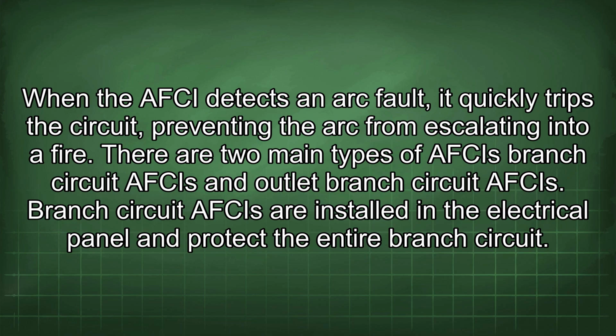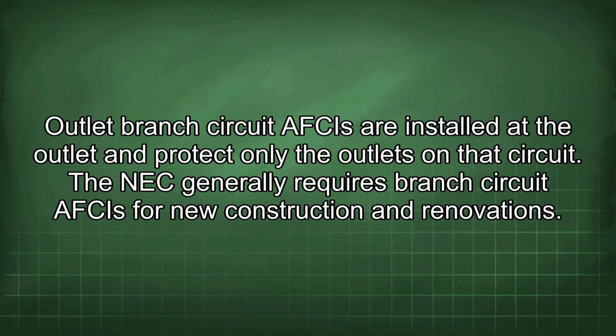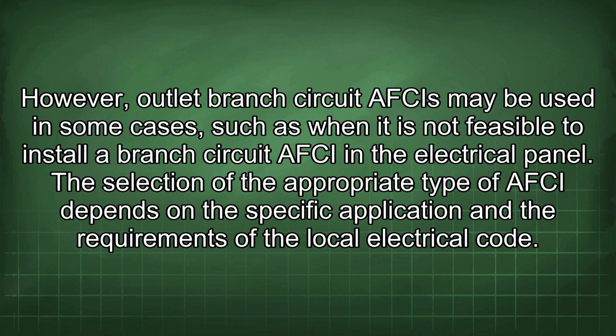There are two main types of AFCIs: branch circuit AFCIs and outlet branch circuit AFCIs. Branch circuit AFCIs are installed in the electrical panel and protect the entire branch circuit. Outlet branch circuit AFCIs are installed at the outlet and protect only the outlets on that circuit. The NEC generally requires branch circuit AFCIs for new construction and renovations. However, outlet branch circuit AFCIs may be used in some cases, such as when it is not feasible to install a branch circuit AFCI in the electrical panel. The selection of the appropriate type of AFCI depends on the specific application and the requirements of the local electrical code.